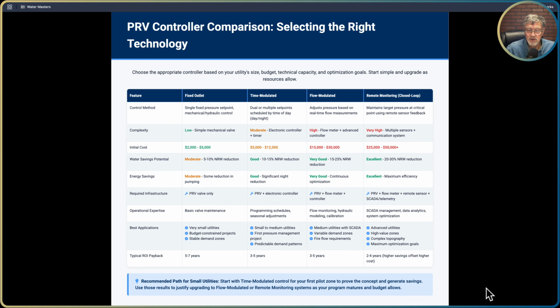And so the best applications, generally, I'm throwing out the fixed outlet just because I don't think anybody should really be using that. So time modulated, small to medium utilities, first pressure management type of project should be time modulated because you can get used to it, and then you can start to roll out some of these other ones. So predictable demand patterns is what you need for that. Flow modulated is going to be medium-sized utilities with SCADA, variable demand zones, and fire flow requirements. So that's probably going to apply to the small guys too. It just gives you more accuracy and a little bit better flow modulation than just the time modulated.